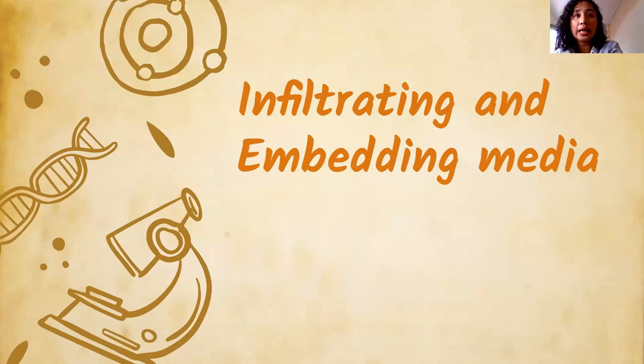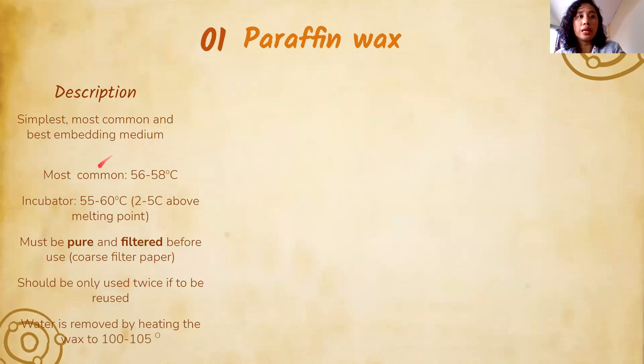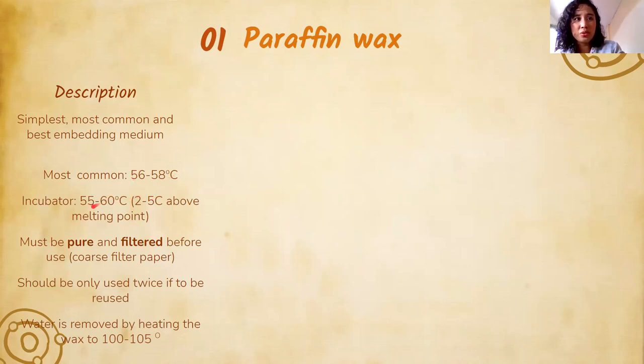Now let's tackle infiltrating and embedding media. First and most important is paraffin wax — the simplest, most common, and best option, routinely used in the laboratory. The most common melting point is 56 to 58 degrees Celsius. The paraffin oven maximum is 60 degrees Celsius, and you set it 2 to 5 degrees higher than the melting point.